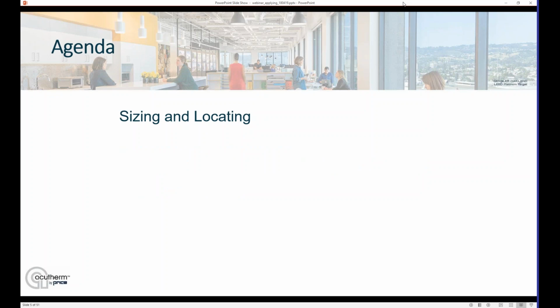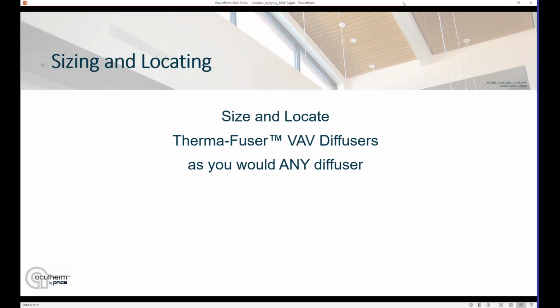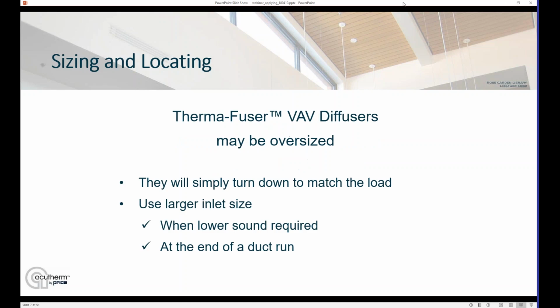First, sizing and locating of the diffusers. The short answer here is you size and locate them as you would any diffuser. Kind of a cop-out answer, I know, but there are some benefits right off the bat here for VAV diffusers, and that is they may be oversized. You don't have to worry about that because they have a VAV damper and they're going to simply turn down to match the load in the space.